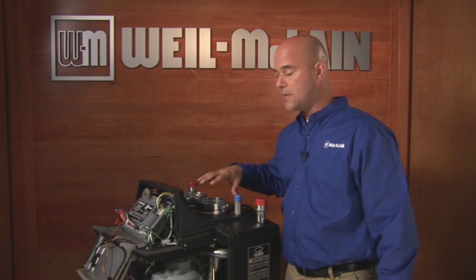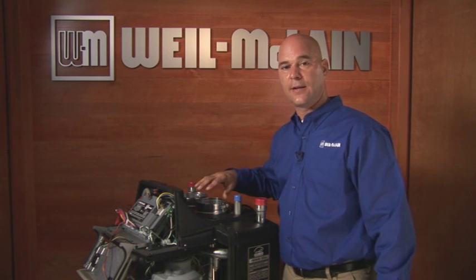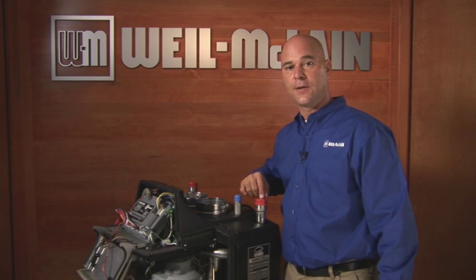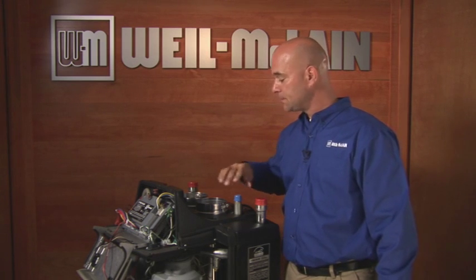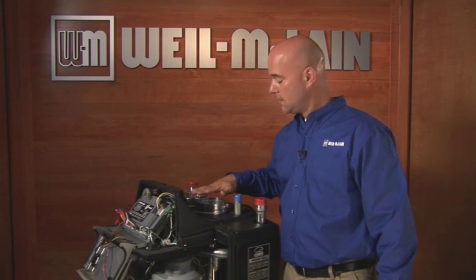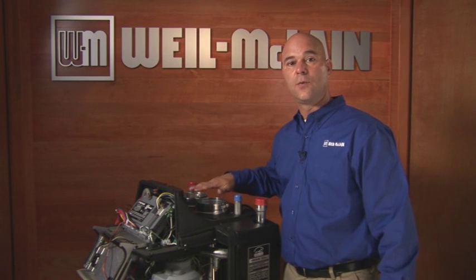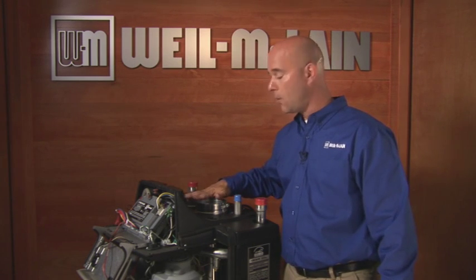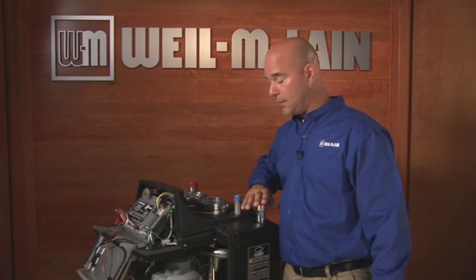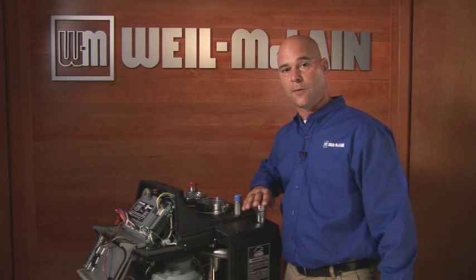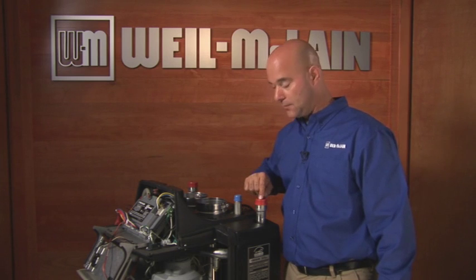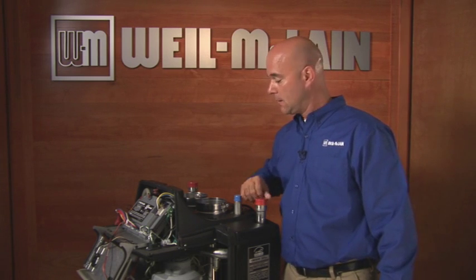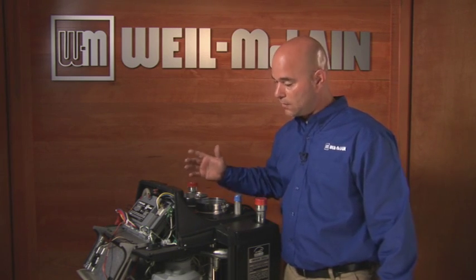So, know what size boiler you're installing, double check it against the manual to see if you have to increase the supply and return piping or if you can decrease the exhaust piping, which will save in the cost of your exhausting. But we need to make sure the flow rate through the boiler is correct. Double check the manual to make sure that this is correct. And that's the components on the Ultra boiler from top to bottom.